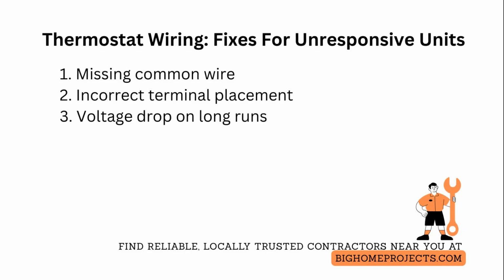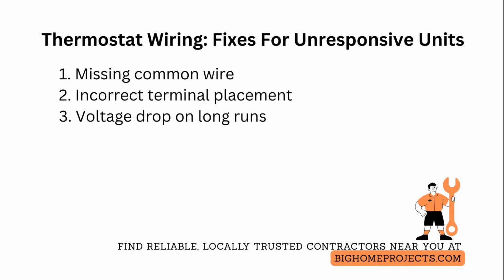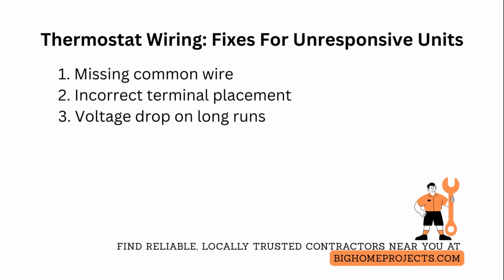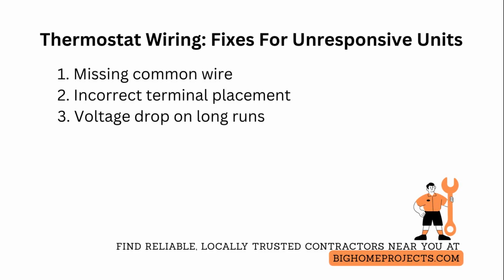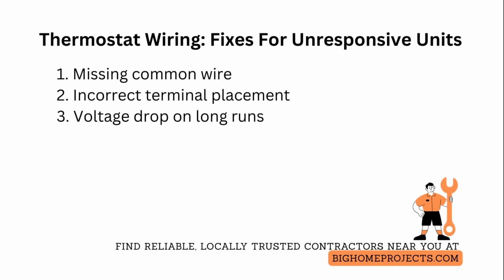One of the next frequent problems is incorrect terminal placement. People put wires under the wrong screw or mix up white for heat and yellow for cooling. Correct by labeling each conductor at the furnace, following color to function maps, and confirming with the thermostat wiring diagram.